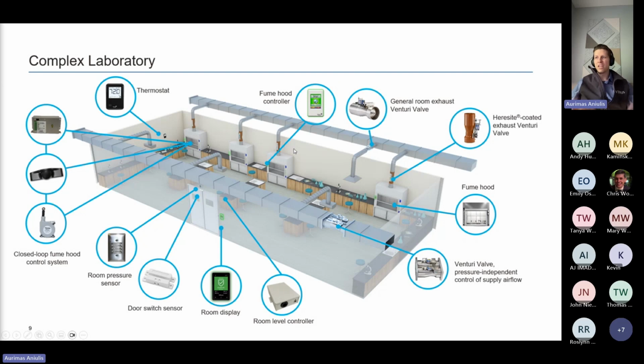And all of this is done for safety, right? The number one priority here is safety of the user. In order to make sure the fume hood is safe, we have an individual fume hood control on each fume hood. Each fume hood has its own exhaust air valve. The brown is a Heresite phenolic coating to prevent corrosion from any chemicals that are being mixed or used inside of the fume hood.